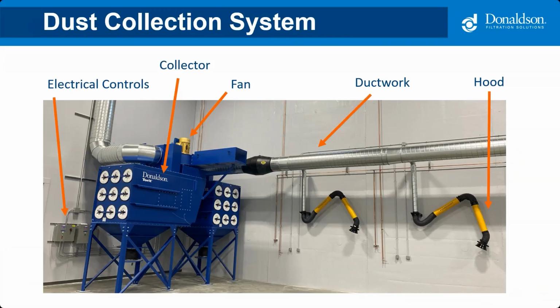Here's a real example of a dust collection system. Well, actually two of them next to each other. This is for a welding application that was recently installed. Obviously the weld curtains aren't set up yet, but you kind of get a feel for the setup. You can see the fan at the top with a silencer for noise reduction, the dust collector, these are cartridge collectors, the ductwork, extraction arms with bell mouth hoods at the end of them, and the electrical controls mounted on the wall.